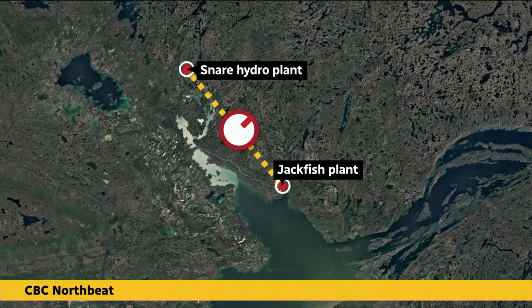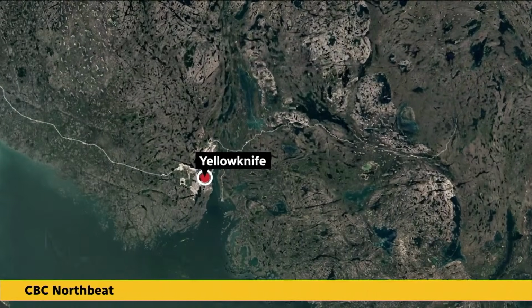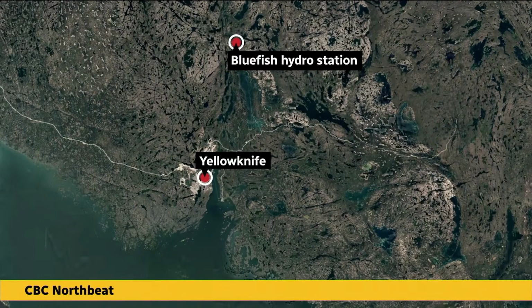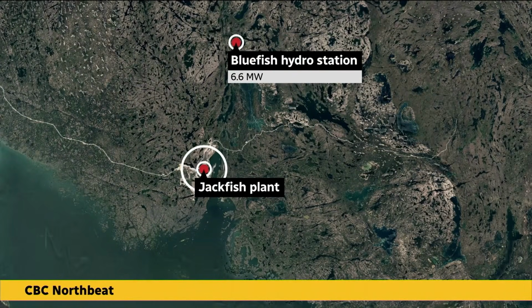Let's go back to the map. If something goes wrong with the Snare Hydro line, there's another hydro station about 40 kilometers from Yellowknife called Bluefish Hydro, with 2 turbines totaling 6.6 megawatts. Then there's Jackfish, a diesel plant that can generate 26 megawatts, just short of the city's peak usage. During a traditional yearly shutdown, or if there's an alarm or an issue at one of the hydro sites, we would seamlessly bring on a diesel genset. You wouldn't even know there was a disruption of power in the city.